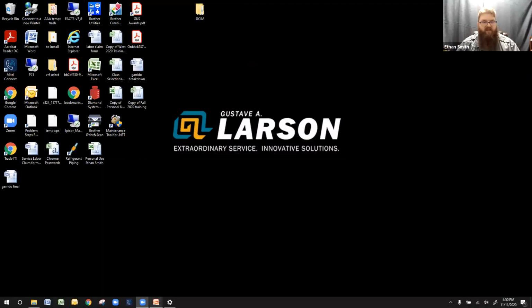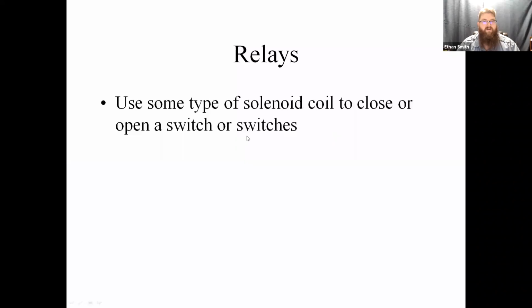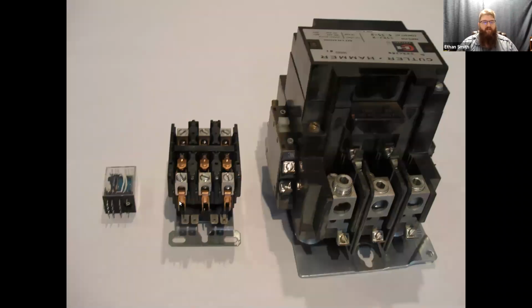Let's go back to this presentation here. So we've got our two components, solenoid and a switch. We talked about troubleshooting. So contactors. Contactors are the same thing as a relay. Generally, you just have higher amperage contacts. So we could even call that little relay there a contactor. But typically, we're talking about stuff like this that has multiple high amperage ratings, all the way up to big mag starters. Okay, it's just a big contactor, guys.